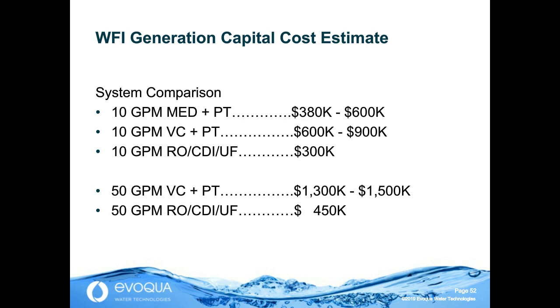For vapor compression, a small VC still is much more expensive than a similar size multiple effect still. That is typical. The pre-treat may be simpler. So again, there's a range. But the membrane-based system, and that would be based on hot water sanitizable, all stainless hygienic construction, and it may be half to a third of the capital.